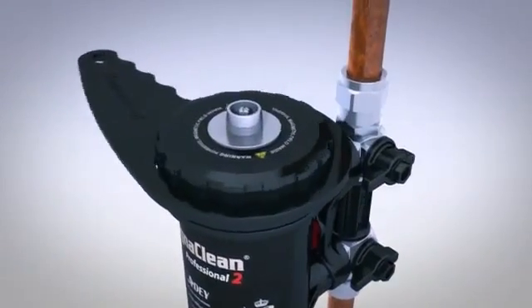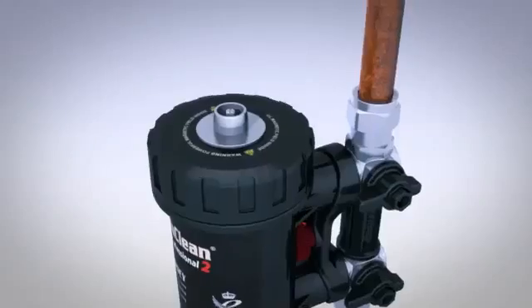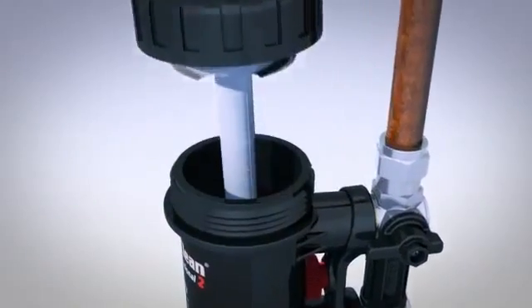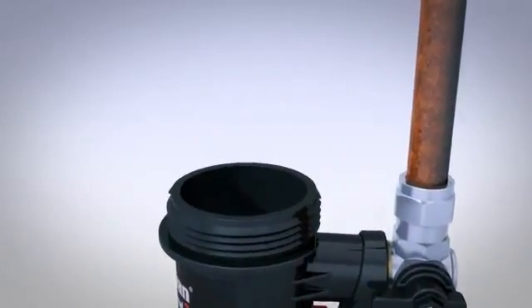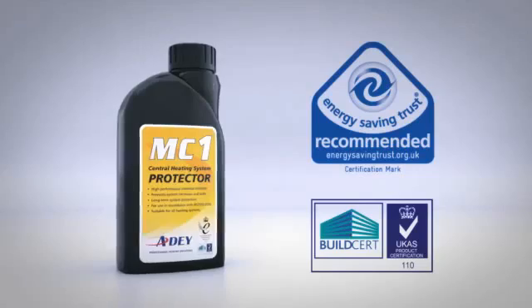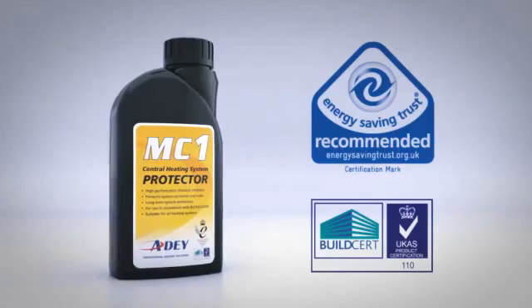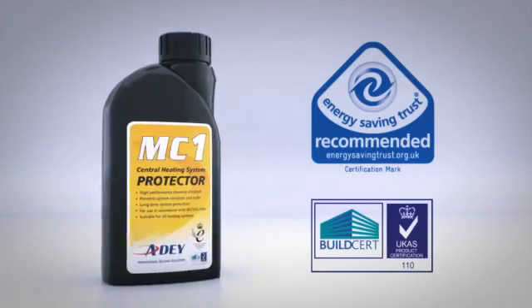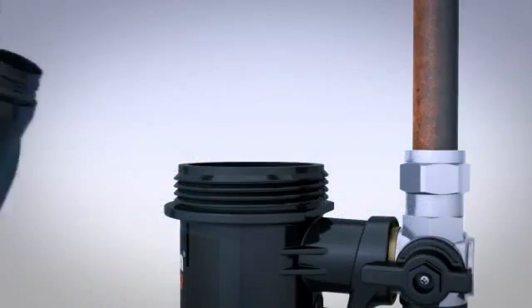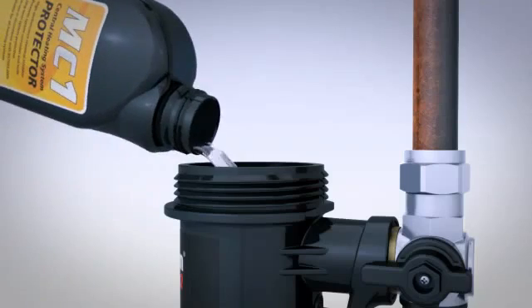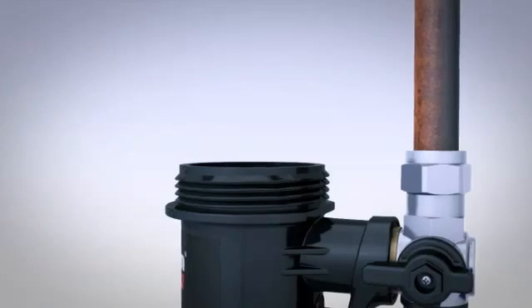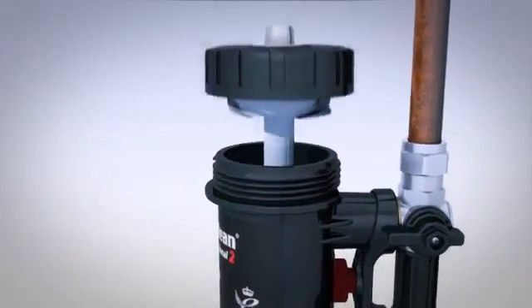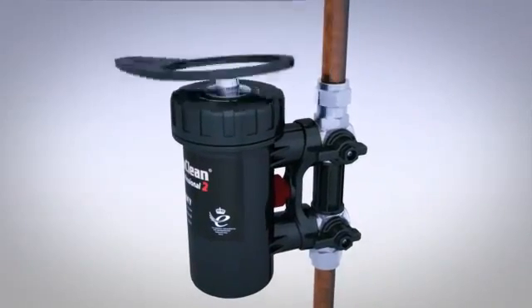Using the spanner provided, unscrew the canister lid and remove the magnetic and non-magnetic capture assembly. To further protect the system, chemical dosing with MC1 protector is recommended. Use the MagnaClean canister as a dosing vessel to add the inhibitor. Replace the lid assembly and secure with the spanner.